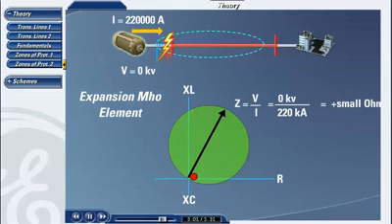To make sure that the MHO characteristic does realize this as being an internal fault that needs to be cleared, the relay recognizes the low impedance of the line, sees that the value is positive, and enlarges the radius of the circle. Since the MHO circle now extends past the origin to include a larger area, the location of the fault is sure to fit in the zone of protection. Therefore, the fault can be cleared properly. Notice, however, that the reach of the MHO circle did not change and still extends out to the end of the original zone of protection.